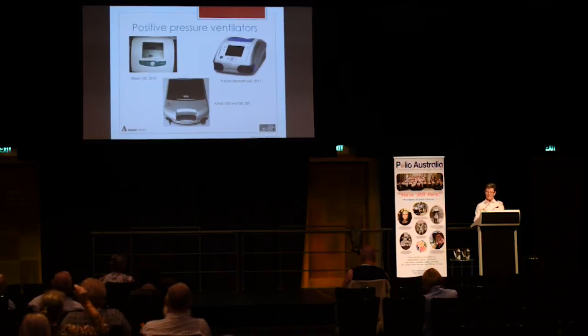And one of the best things about these particular machines is that they will give the clinician and the user a lot of feedback about how the ventilation is going. So they have many different alarms, and with these particular models, instead of having a 2-hour internal battery, they've got a 6 to 8 hour internal battery. So the more demand that's placed on the battery, the less time it will last. But with experience, we know that even with the greatest demand placed upon it, the internal battery will last about 6 hours. So that's really very good, because you can go out somewhere and do something nice in 6 hours where you couldn't get out very far in 2 hours without taking an enormous heavy battery with you.